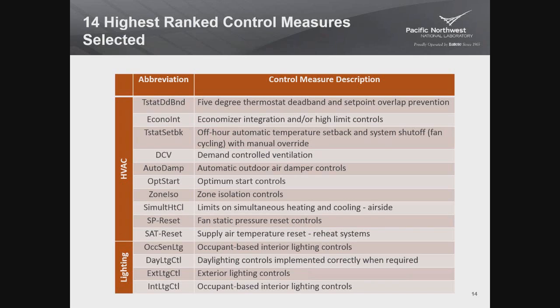Optimum start says that the building control system has to have some smarts in it, some logic that looks at the temperature of the building indoors, looks at the temperature outdoors, and makes a decision about how long before occupancy it has to start up. Zone isolation. This one is a requirement for if you have an HVAC system that serves lots of different spaces. There has to be the ability to isolate individual zones so that if some zones have different schedules than the others, you close those dampers automatically, and you're not providing conditioned air to those zones that are not occupied.